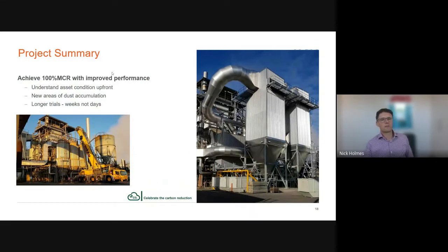So in summary, we managed to convert the boiler from coal to biomass, achieving 100% MCR. We did actually manage to lift the performance slightly from where it was because it was constrained with some of the older assets. A key point to understand, if you're going to convert, is how good a condition your boiler is in. Until you pull it apart, you can be confronted with some surprises of how poor condition some bits of equipment are in.